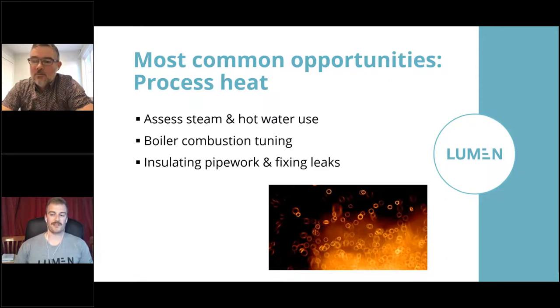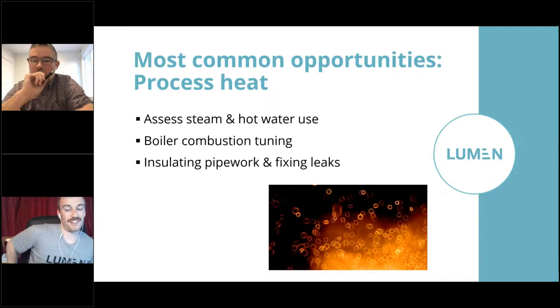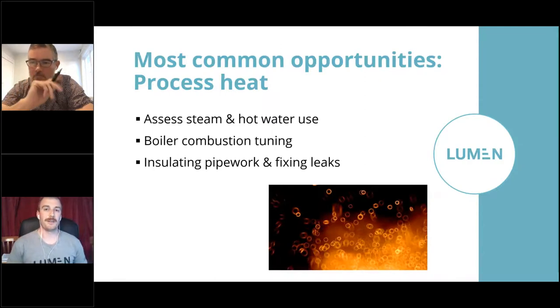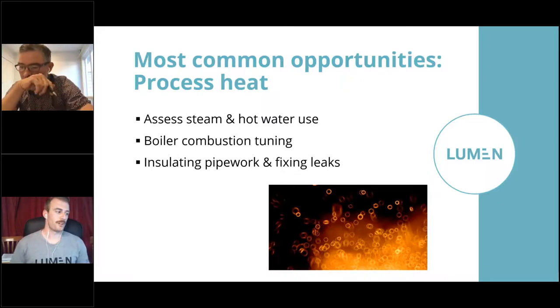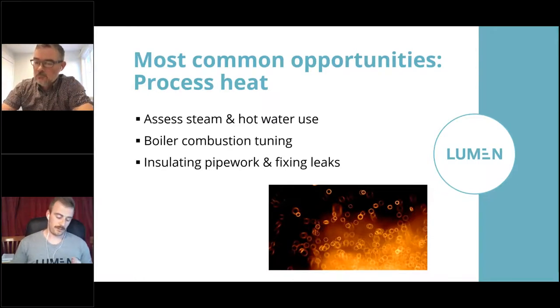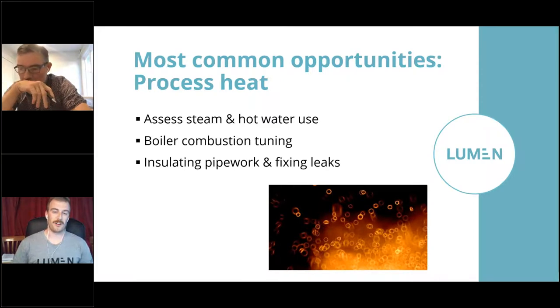You can get a huge amount of benefit out of these relatively basic systems optimization tools. We've got a really good example with a client last year. So the client came to us with a problem. They had three coal boilers, one big coal boiler and two small coal boilers. And the consents for the two small boilers were running out at the end of 2019. And so they said to us, we need to find a replacement for those, ideally some low carbon options. And we decided, hold on a sec, let's see if we can reduce the consumption first. So using the three tips on this slide, we've now got to the point where they can actually meet the steam load with that one large coal boiler. So the site's using way less coal than it was before. They didn't have to stump up any capital to replace those two small boilers because they don't need them anymore.